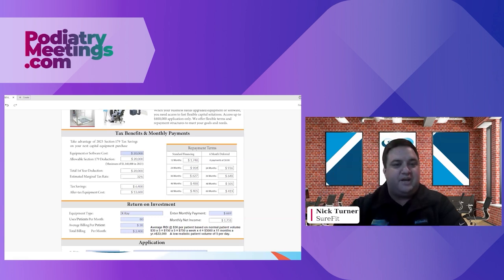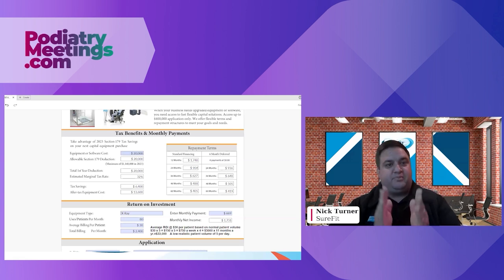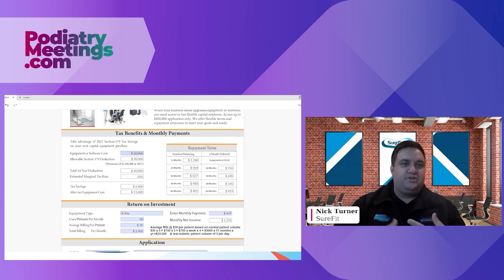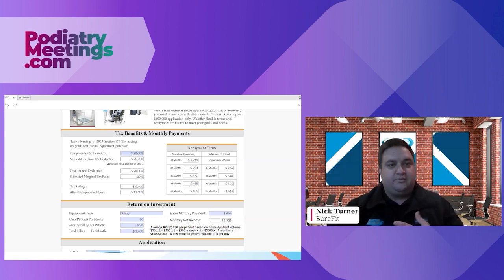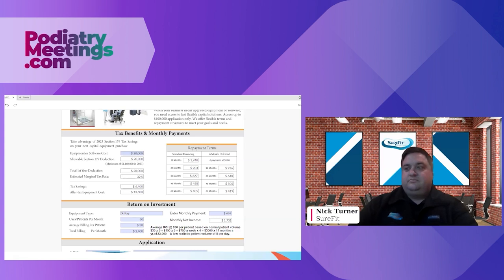The panels themselves, depending on the type and size you get, those could range from 15 to 17K up to 22K. So typically when I see somebody doing a complete portable package, a portable X-ray, and they need a panel, software, laptop, the stand, everything, usually it's coming in between 31 and $33,000. Again, it's not a small number, but it's the cost of a lower end car in today's market, and it's going to last you probably 6 times as long. From an ROI standpoint, you're going to see it quickly.